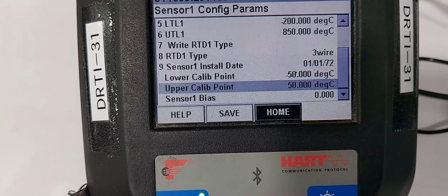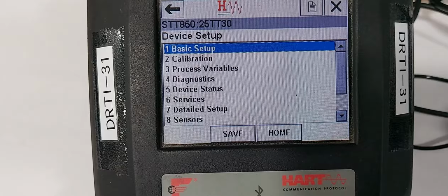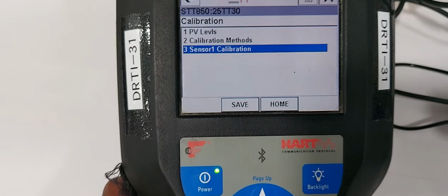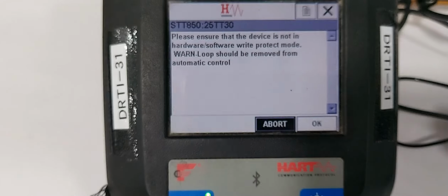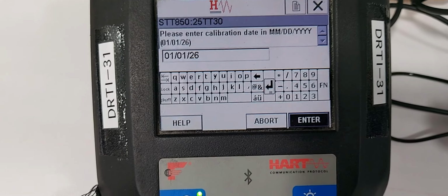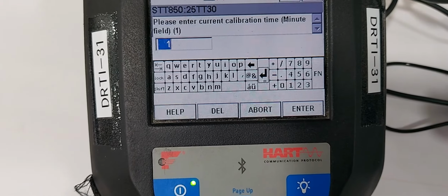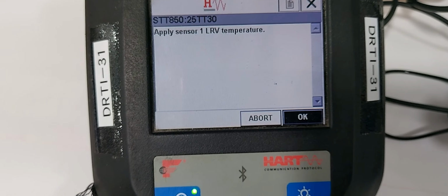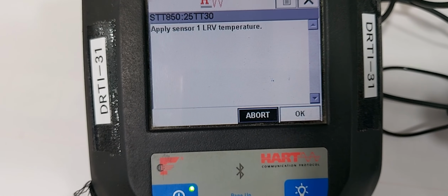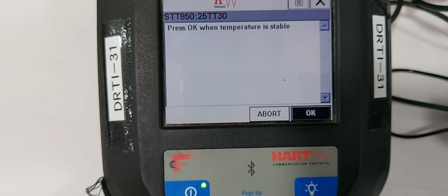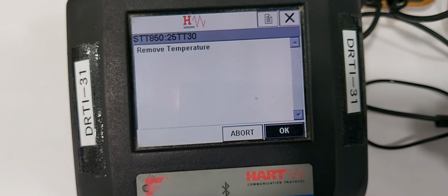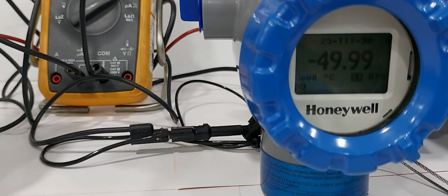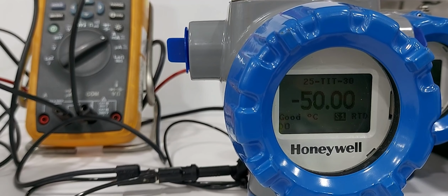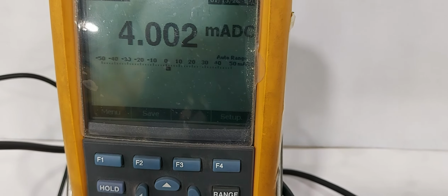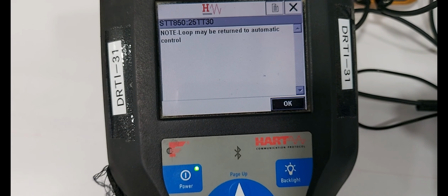Okay, back to the home page. Next we are doing the calibration: device setup, the calibration menu, sensor 1 calibration and the second one, sensor LRV correct, then press OK. Date is correct, time is correct, minute is correct. The sensor 1 temperature is already applied. Then press OK and wait for the temperature to stabilize. Then press OK. Now the zero calibration is completed. Next we are checking the instrument display. The instrument display is showing minus 50 degrees. The reference multimeter is also showing 4.002 milliamps DC. Then press OK.